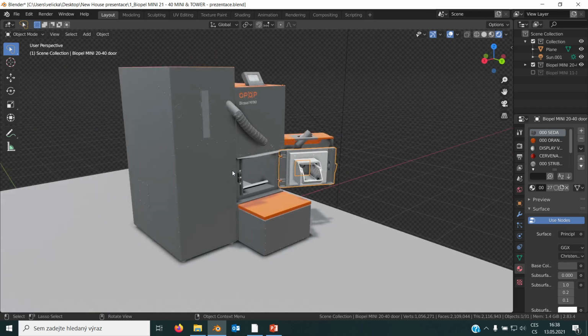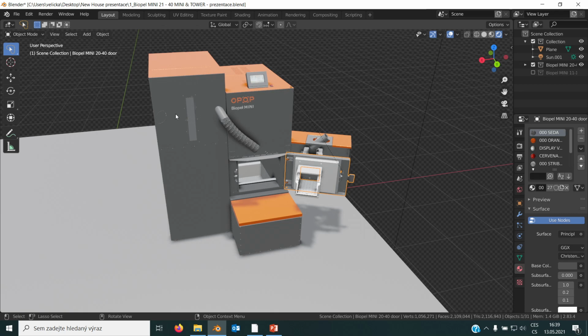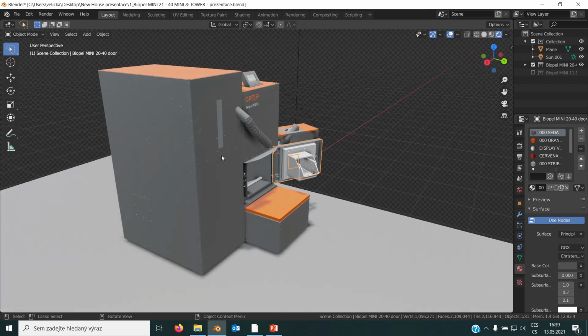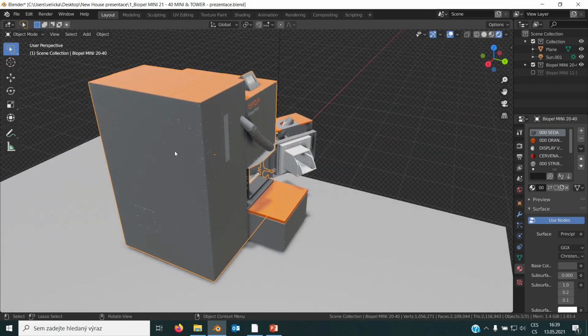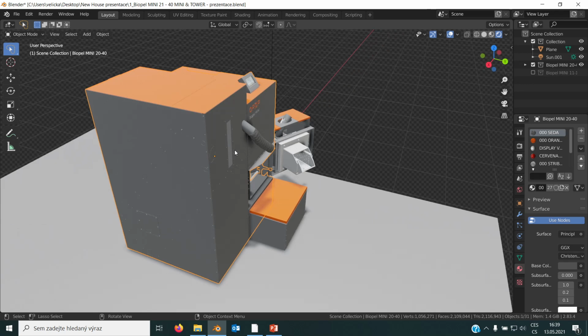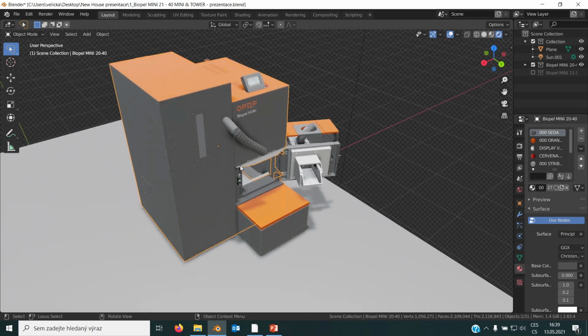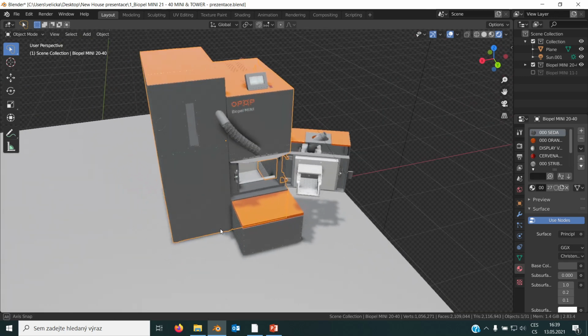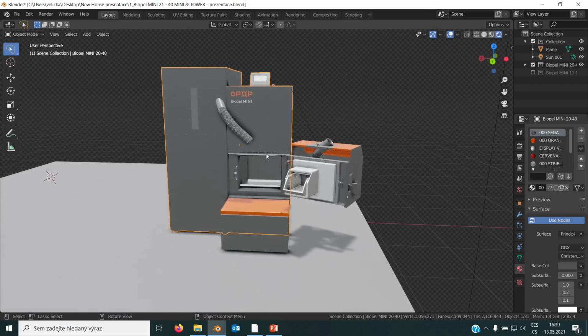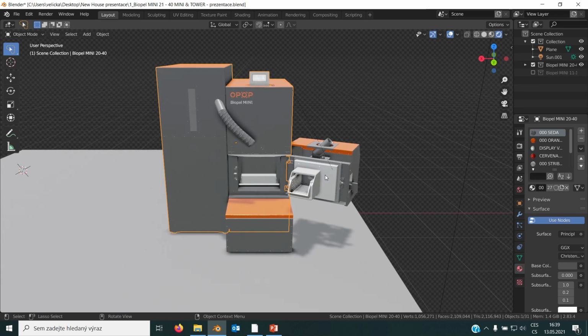You can even open the doors to the left side with the pellet hopper on the left side as well, but in this case you have to move the pellet hopper a little bit back. So there will be a gap between the boiler and the pellet hopper, maybe 15 centimeters. You have to move the pellet hopper to the back, and then you can open the doors at least 90 degrees to the left side where the hopper is. Of course, the standard installation is like this, that the hopper is on the opposite side from where the hinges for the doors are. Okay, so this is the standard installation, let's say.